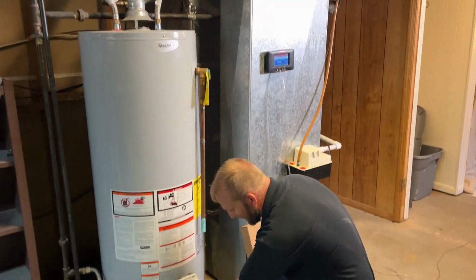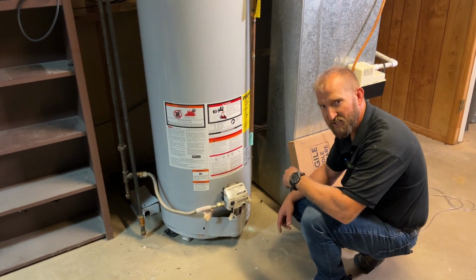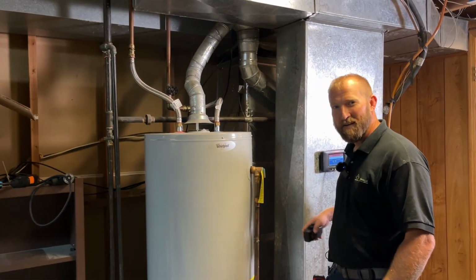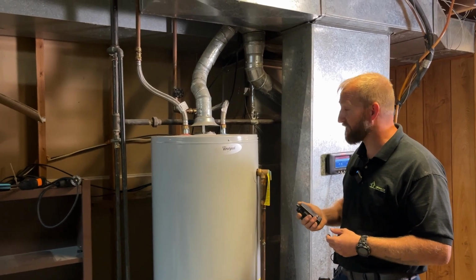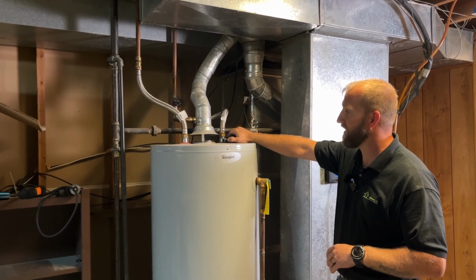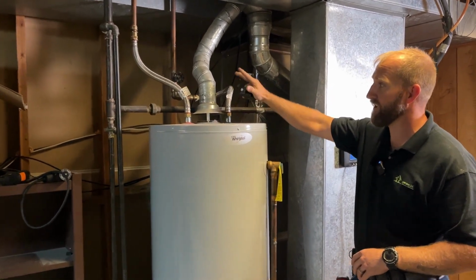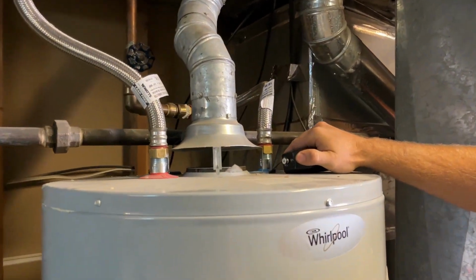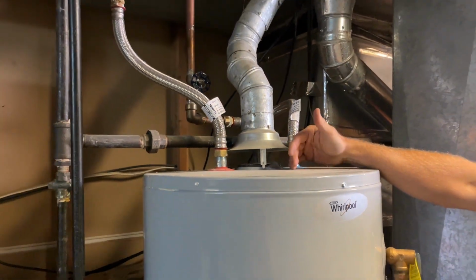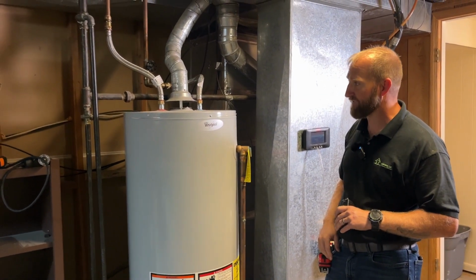So then we're going to go ahead and kick the furnace or the water heater back up to its original setting. It just clicked on. So we're going to wait our 2 minutes for our spillage test. Okay, so once we have our 2-minute mark, we're going to go ahead and check for exhaust. Make sure that you can see the smoke being drawn up the flue. Give a close up on that, so you can see it being drawn up. So we don't have any backdrafting already with the unit. That's a good sign that everything's going to be drafting properly as we go.